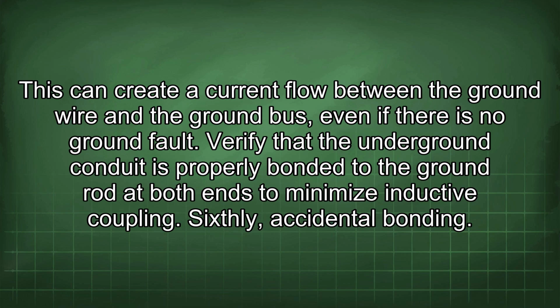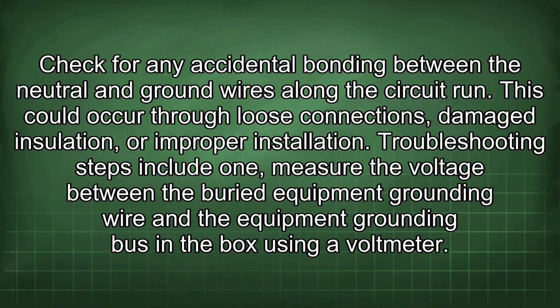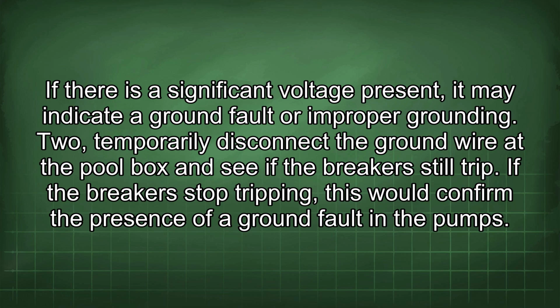Sixthly, accidental bonding. Check for any accidental bonding between the neutral and ground wires along the circuit run. This could occur through loose connections, damaged insulation, or improper installation. Troubleshooting steps include: 1. Measure the voltage between the buried equipment grounding wire and the equipment grounding bus in the box using a voltmeter. If there is a significant voltage present, it may indicate a ground fault or improper grounding.